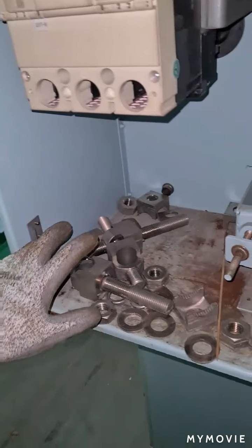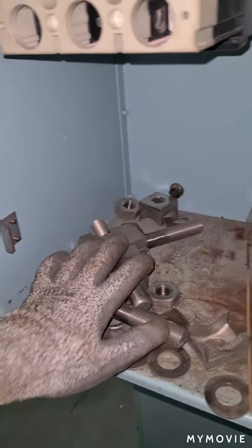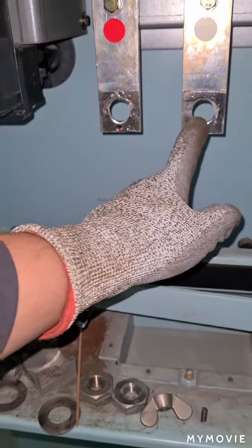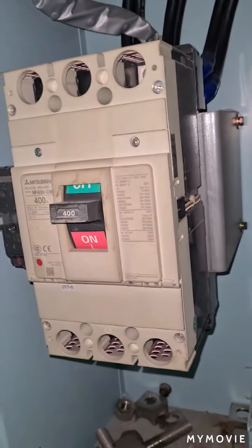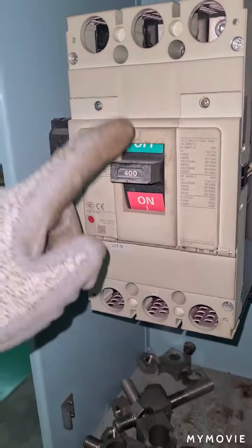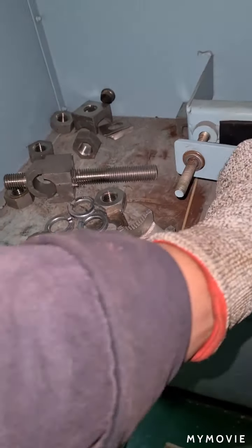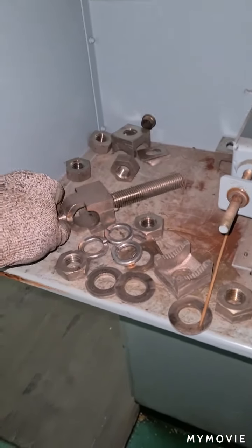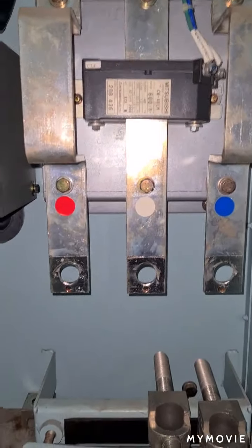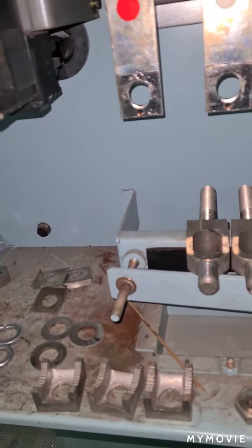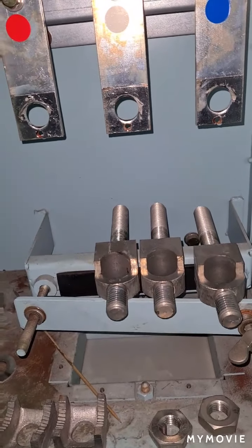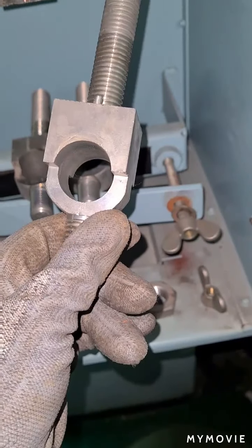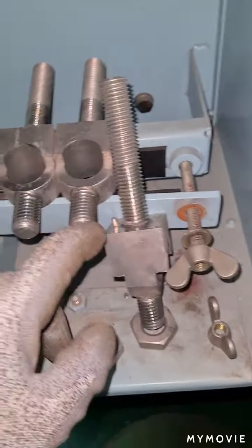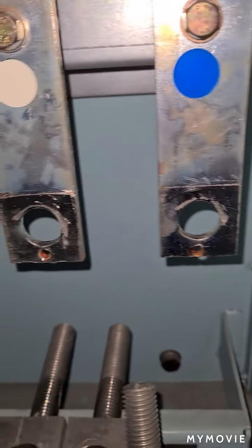Okay guys, I am here in the shore connection box, and I'm going to put all these things back on this bus bar. But first, make sure that there is no voltage on this bus bar, and this is off. Now I'm going to arrange all these things to put back on the original position on this bus bar, because we are going to put back first these terminals. Okay, by looking at it, this pin is going on this hole, so that it will prevent it from moving.